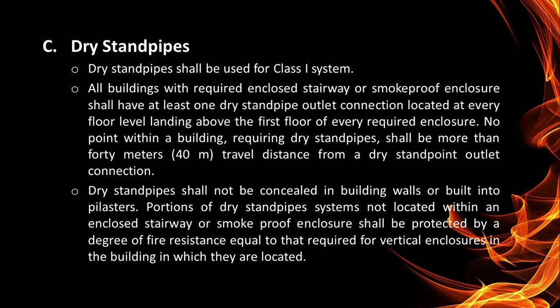So next are the dry standpipes. Dry standpipe shall be used for Class 1 system. All buildings with required enclosed stairway or smoke-proof enclosure shall have at least one dry standpipe outlet connection located at every floor level landing above the first floor of every required enclosure. No point within a building requiring dry standpipes shall be more than 40 meters travel distance from a dry standpipe outlet connection. Dry standpipes shall not be concealed in building walls or built into pilasters.